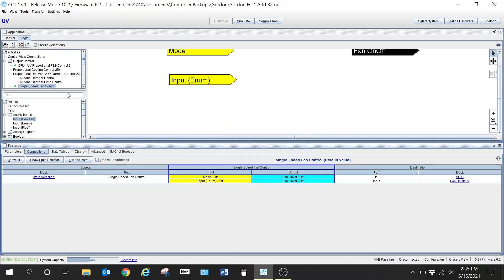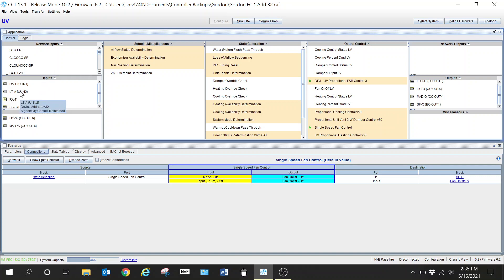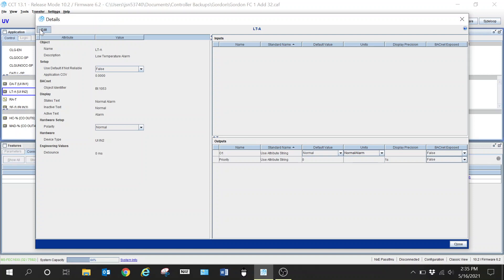So let's cancel out of it. Let's go look at our low temp alarm and see exactly what the state text for it is. I'm just going to double click into it and you will see here the state text is normal and alarm. I cannot change that, that's how this one was configured, it's how it was set up originally. It cannot be changed.